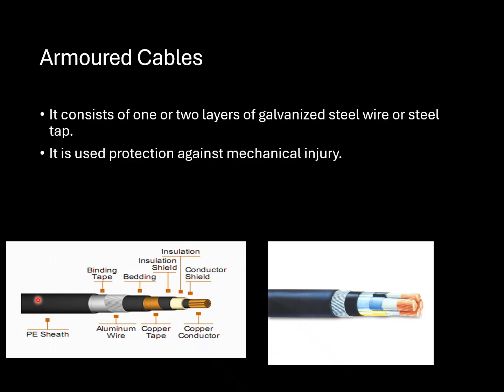Now we'll see the different parts of an armored cable. The outermost is a PVC sheath, then binding tape over that, then aluminum wire, then bedding is used, then copper tape is used, an insulation shield is used, then comes the main insulation and copper shield. They have different purposes. We'll work on that.